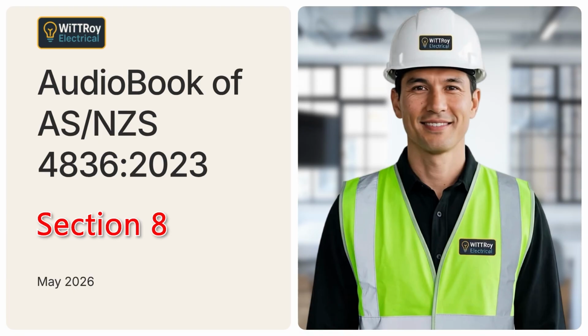Clause 8.3.3 Risk of exposed conductive parts becoming energized. Clause 8.3.3 explains the risk of exposed conductive parts on portable tools becoming energized. Extra care is needed when using portable electric tools or equipment that have exposed conductive parts. These conductive parts may contact exposed energized conductors or live conductive parts. One common example is drilling or cutting into concealed conductors inside a building structure. The metal drill bit, saw blade, chuck, or other conductive part may contact a live conductor. That can make the tool dangerous and may expose the worker to electric shock.